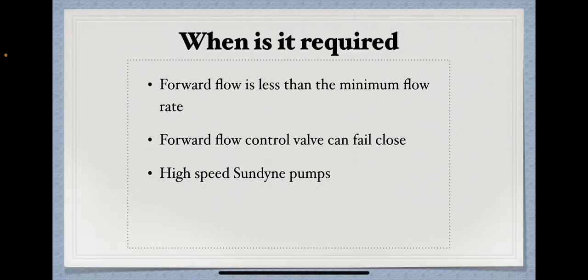When is minimum recycle provided? A minimum flow bypass across the centrifugal pump is provided if the continuous forward flow is below the pump minimum flow at some operating point.